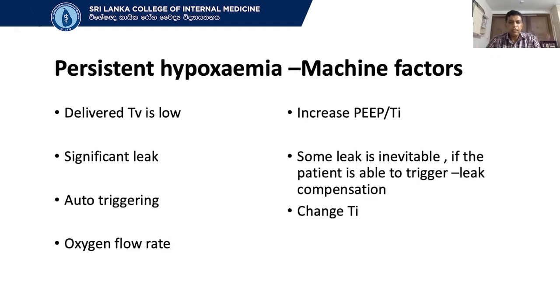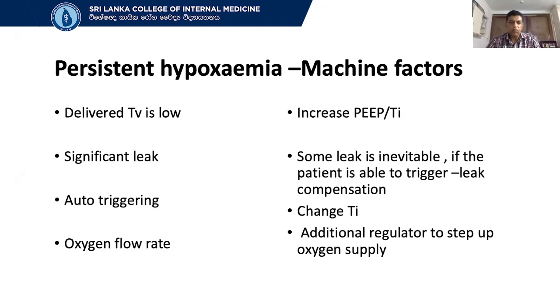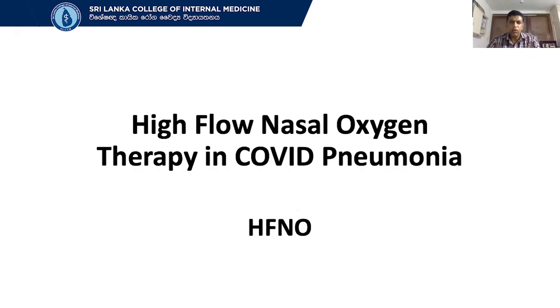Then the other thing is if the patient is auto triggering, the patient's spontaneous rate, so you need to change the inspiratory trigger. And also if the patient is hypoxic, you can increase the flow rate. Above 15 is what we can give with a conventional regulator, but there are flow meters that you can increase the flow rate to 25 liters. So if you have that facility, use that as well. So this is what you should do when a patient is persistently hypoxemic while receiving NIV. It could be patient factors, which are very little. It could be what we say is tubing or interface factors. It could be something to do with the machine, which we need to see which one is contributing to hypoxia.